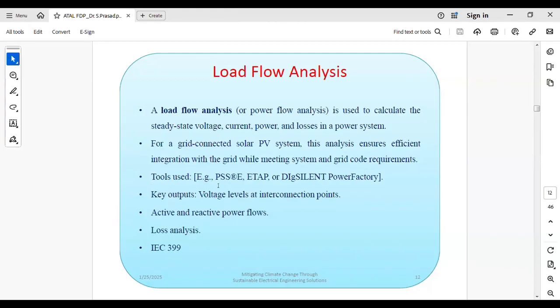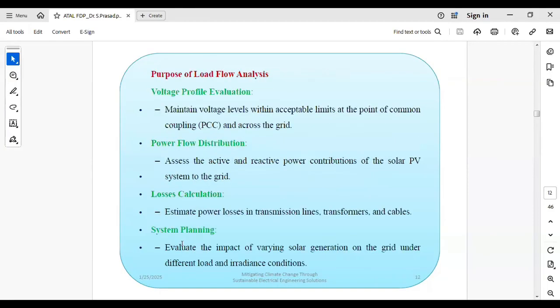And what are the different tools we are using? We are using PSSE, ETAP, DIgSILENT, and PowerFactory. These are the different power system software tools we are using to conduct the load flow analysis. And the standard we are following is IEC 399 for load flow analysis. So you have to check the voltage profile at the point of common coupling, PCC or POI point, then the flow distribution, active and reactive power distribution of the solar PV system to the grid, then loss calculation and system planning, based upon that, to evaluate the impact of varying solar generation.